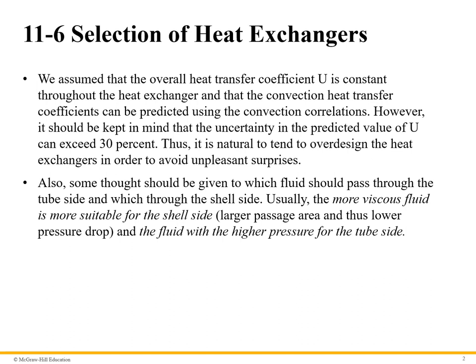In the previous sections, we assumed that the overall heat transfer coefficient U is constant throughout the heat exchanger, and that the convection heat transfer coefficients can be predicted using the convection correlations. However, it should be kept in mind that the uncertainty in the predicted value of U can exceed 30%.